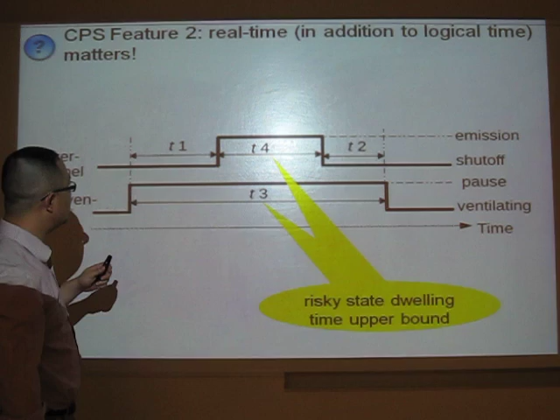And then we have this enter risky safeguard interval requirement and exit risky safeguard interval requirement. In the ventilator laser scalpel example, it's like this. After the ventilator has been paused, the laser scalpel cannot immediately shoot laser, because this can still trigger fire, because there is still a lot of oxygen in the trachea. You must at least wait for T1 seconds before you can shoot laser. So this T1 seconds minimum requirement is called the enter risky safeguard interval.